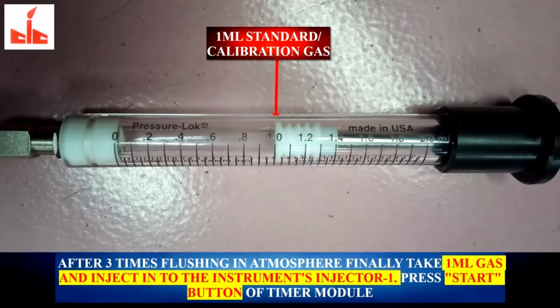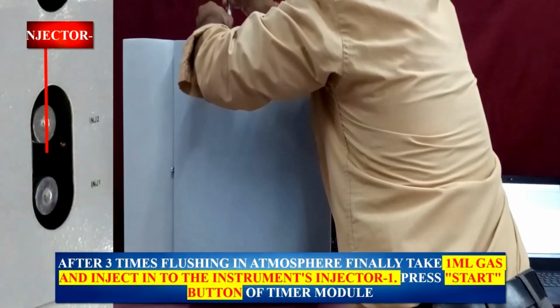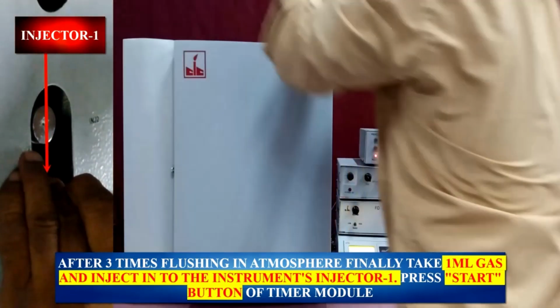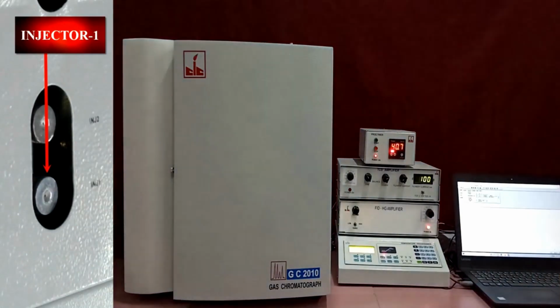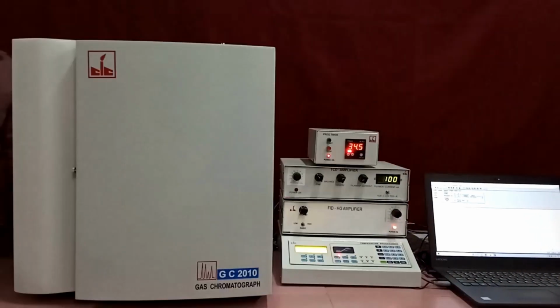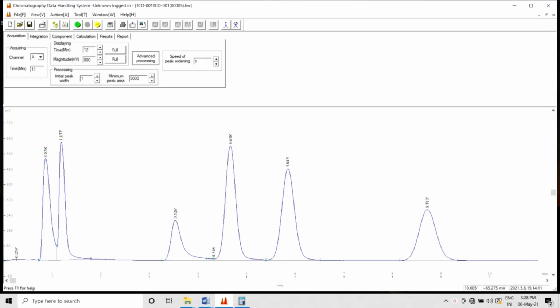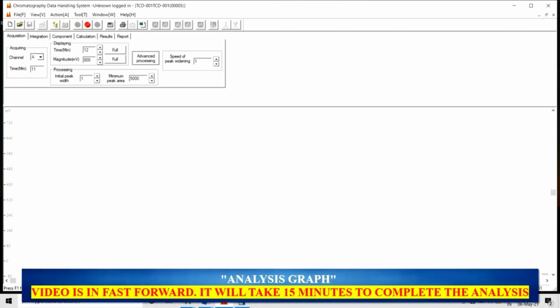After 3 times flushing in the atmosphere, finally take 1 ml gas and inject into the instrument's injector number 1. Then press the Start button of the timer module. Acquisition will start, and the graph can be seen on the analysis window of the software. Analysis graph. The video is in fast forward mode, for demo purpose only. Actually it will take 15 minutes, or the instrument's final time settings, to complete the analysis.